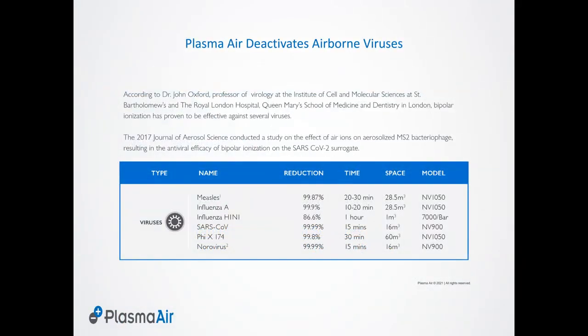I put this slide up because plasma air deactivates airborne viruses. As one of the previous presenters mentioned, viruses are actually easier to kill than some mold and bacteria, but they travel quickly and spread quickly, et cetera. So you get excellent results with some of the legacy technologies, and even though ASHRAE calls bipolar ionization an emerging technology, there are some things that are emerging about it, like ozone-free options that weren't available back in the Sharper Image days.